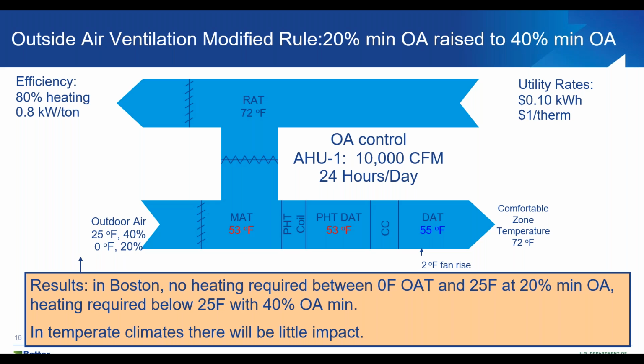And the flip side, we're in the winter now, but during the summertime, the opposite would have happened where you could have issues with humidity and mold conditions. So you have to be careful with how much outside air you're putting through the building. Now, in a temperate climate, there's going to be little impact, because there's very little heating or cooling. So this is more impactful in an environment that's very hot and humid or very cold. Next slide, please.